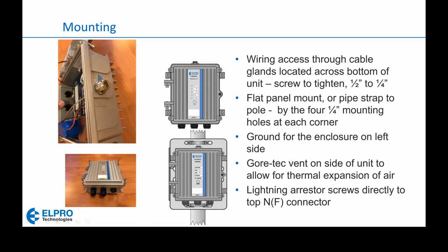Now we have a lightning arrestor that screws directly to this connection right here, and that is a type N threaded connection. And we have a new option in our price list of a special lightning arrestor that has N female and N male connectors. So it threads directly onto this. You then have to weatherproof this connection with electrical tape and the 3M weatherproofing tape, just as you would weatherproof all of your other coaxial cable outdoor connections. So we do have to make sure this has a good seal around that.